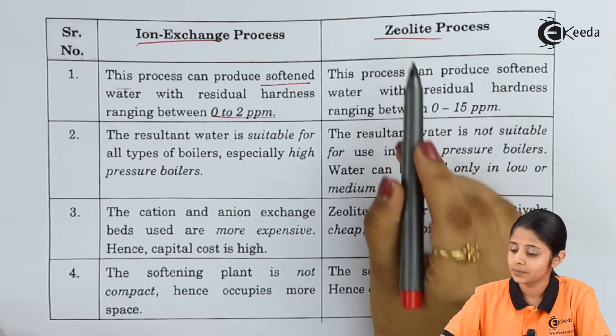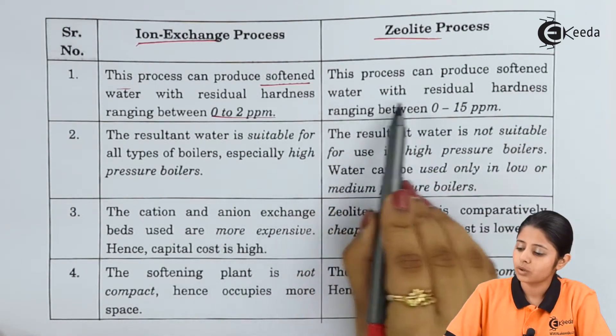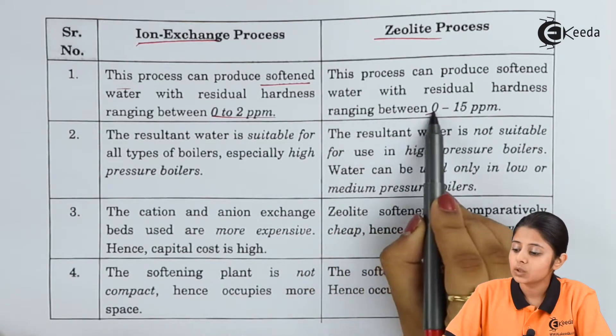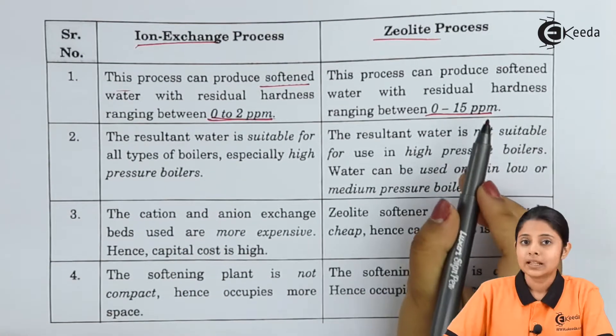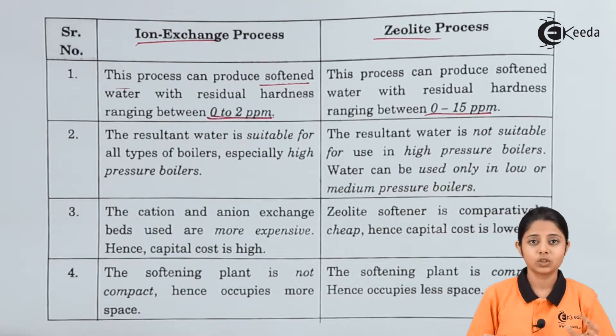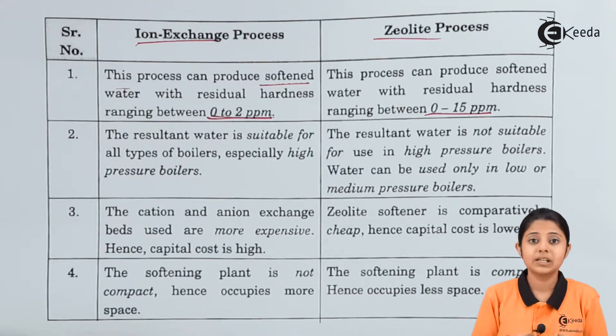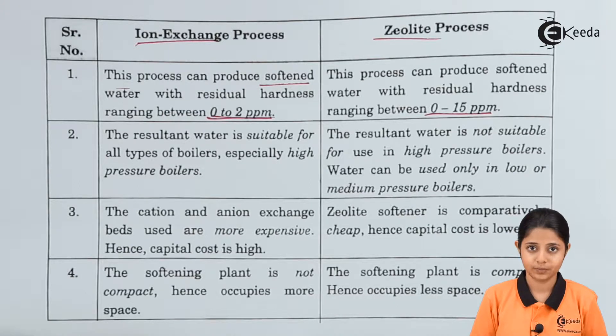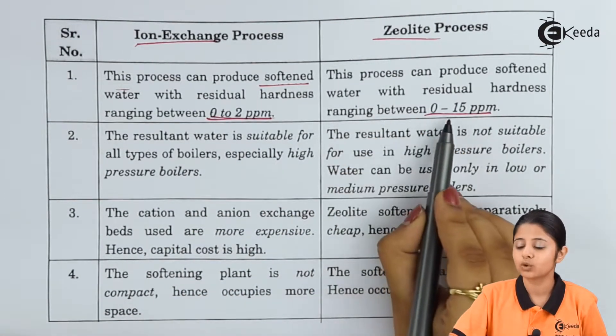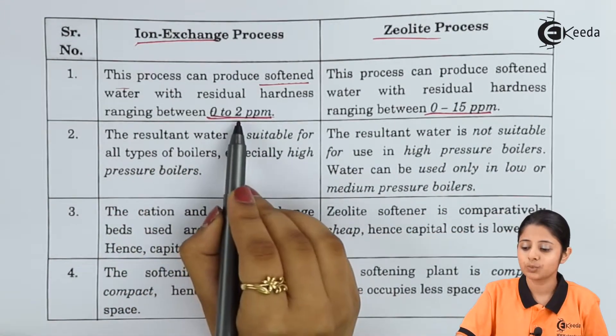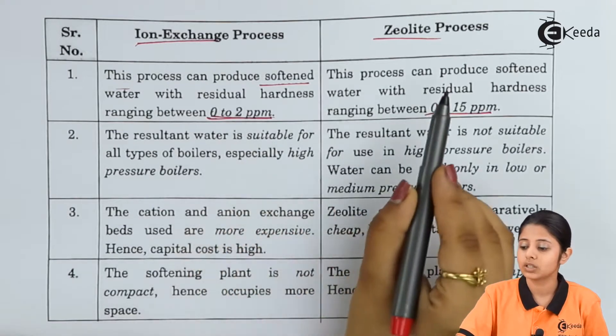For the zeolite process, the softened water produced has a residual hardness ranging between 0 to 15 ppm — meaning for every million parts of water there will be up to 15 parts of impurities. Comparing both: the ion exchange process gives 0 to 2 ppm, while the zeolite process gives 0 to 15 ppm. Therefore, the ion exchange process produces better quality water compared to the zeolite process.